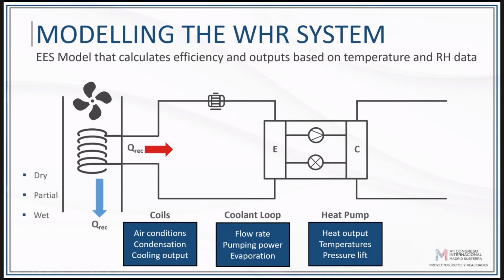And what the model is able to do is to estimate and predict if the coil surface would be fully dry, partially wet, or fully wet. And this allows us to understand how much of the cooling effect is actually sensible and is causing a reduction in temperature, and how much is associated with just reducing the humidity of the air. The model also considers how much additional power would be required to run the reversible fan based on the pressure drop of the system. And we calculate energy and mass balances across critical points of the system.